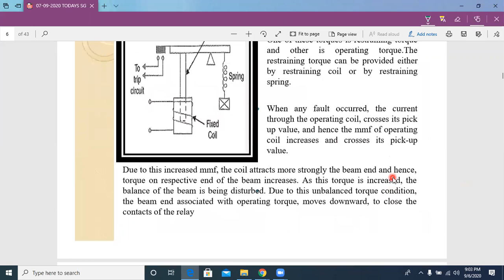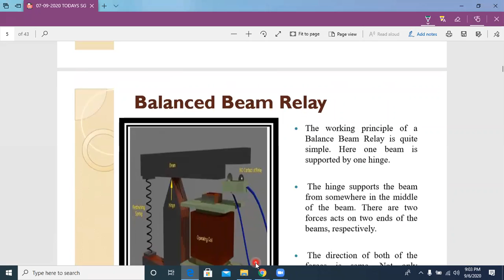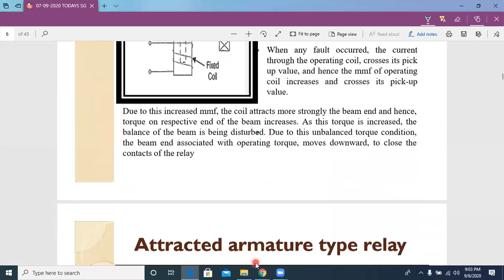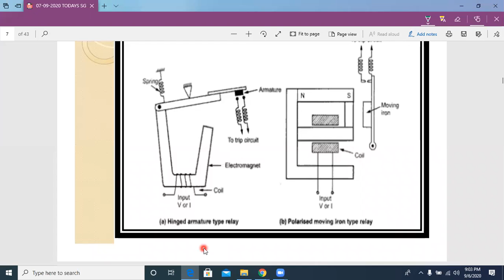So, electromagnetic attraction type relays. We have seen three examples. The first one is the balanced beam type relay, the second one is the hinged armature type relay, and the third one is the polarized moving iron type relay. In all these three different relays, the operation is the same. In these three types of relays, we can see restraining torque and operating torque. In the normal case, the restraining torque value is equal to the operating torque. When the fault happens, the operating torque dominates the restraining torque. Due to that, the trip coil circuits are closed. Okay, so this is the explanation.